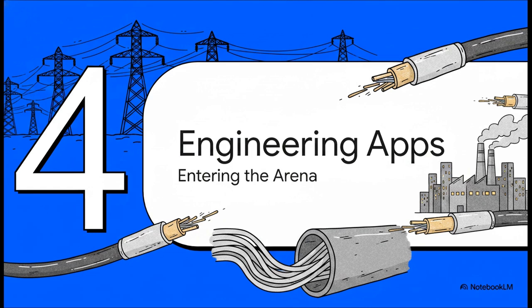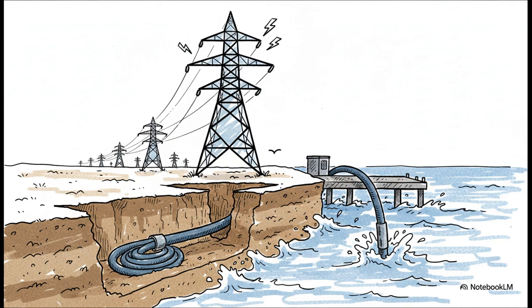Let's step into Section 4, Real-World Engineering Applications. This is where the theory meets massive infrastructure. For heavy infrastructure, XLPE is the undisputed champion. If you're dealing with medium voltage networks, so like 11 kV up to 33 kV, or high voltage transmission, XLPE is your go-to, no questions asked. Even on low voltage networks, it's heavily utilized for those main incoming feeders coming off massive power transformers. Basically, if a cable is going into an underground trench, direct burial, or a really harsh marine port environment where moisture is a constant threat, you're using XLPE.